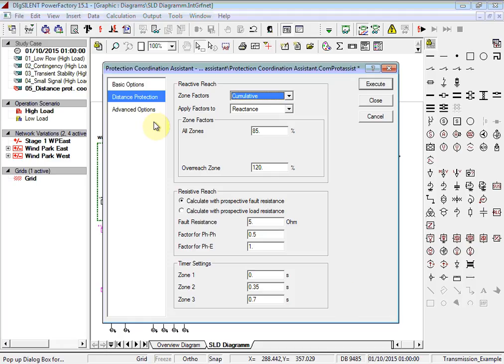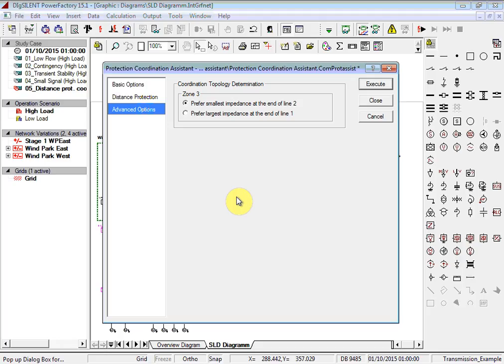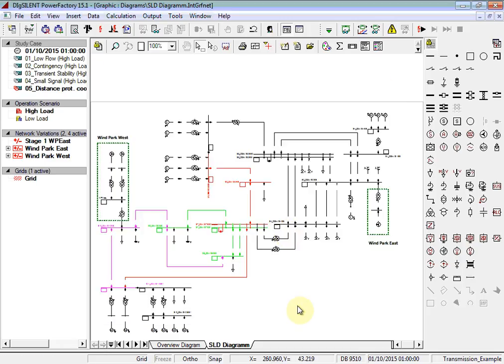There is also an advanced option for the calculation of zone 3. This option determines whether the assistant tends to limit zone 3 to the second impedance or to an impedance beyond the second impedance. Leave it with the default setting and choose the option Execute. In the background, the Protection Coordination Assistant calculates the zone settings. We can view the results of the calculation by pressing the Output of Coordination Result button.